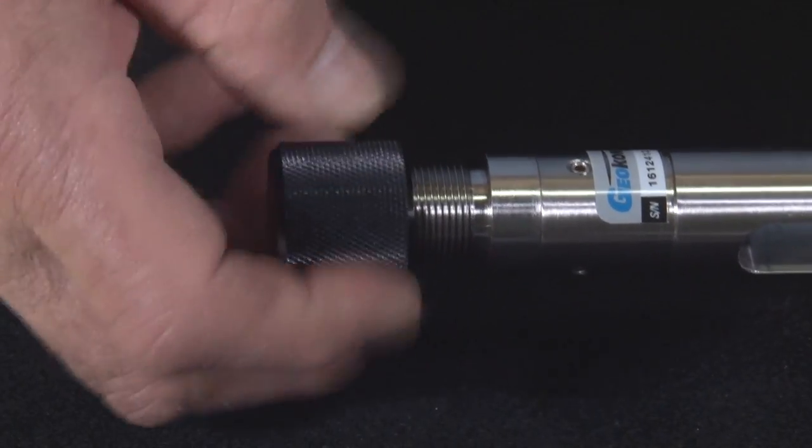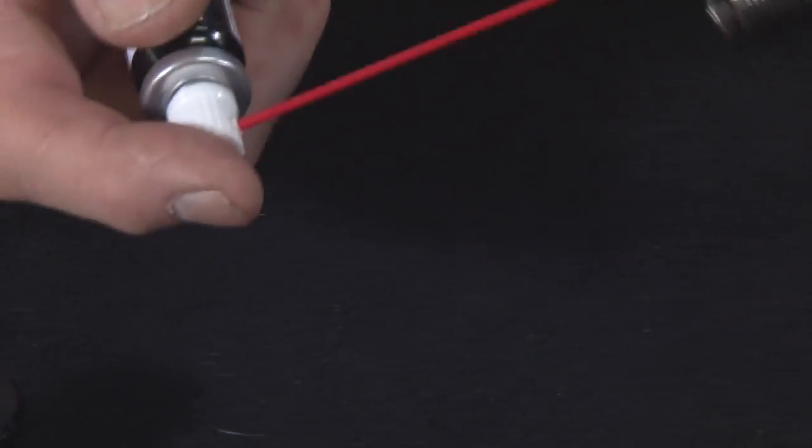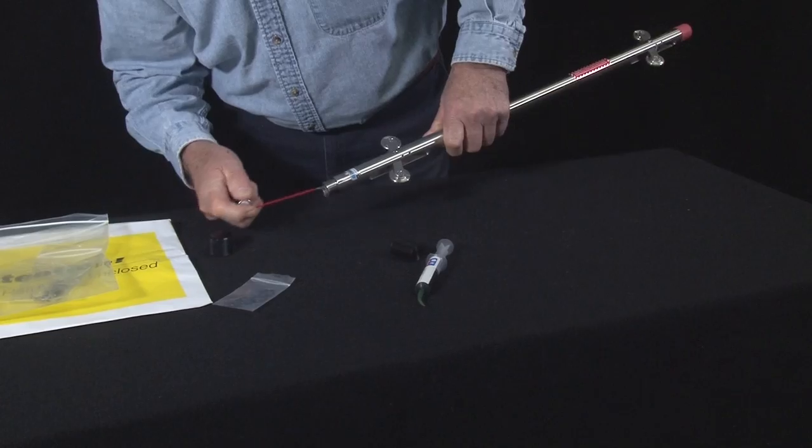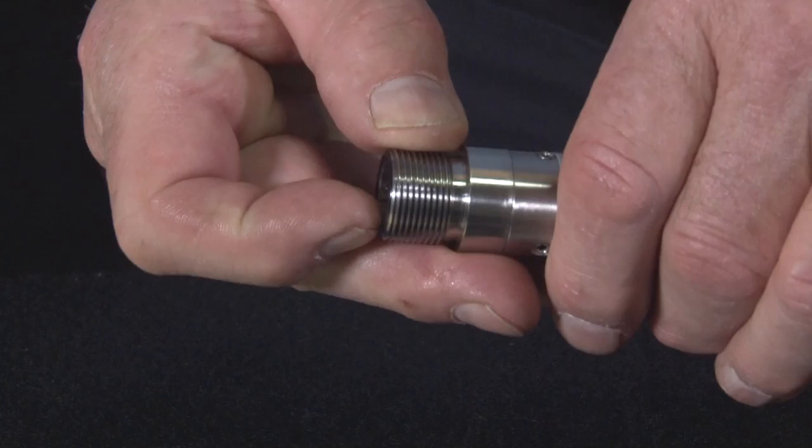Unscrew the protective cap from the probe connector. Lightly spray the interior with the supplied cleaner. Drain out the excess. Remove the O-ring from the connector and replace with an unused ring.